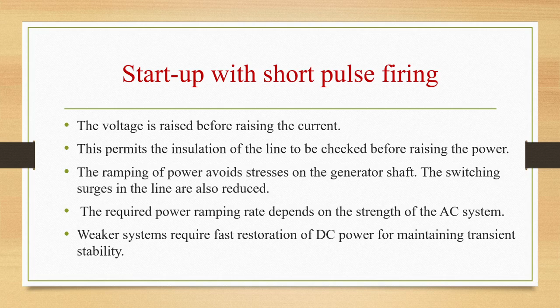Weaker systems require fast restoration of the DC power for maintaining transient stability. Unfortunately, high ramping rates in such cases can give rise to large voltage drops due to the requirement of reactive power at the converter. Such voltage drops can lead to commutation failure at the inverter. Permissible ramping rates may vary from 2 to 10 per unit per second, implying a startup time of 100 to 500 milliseconds.